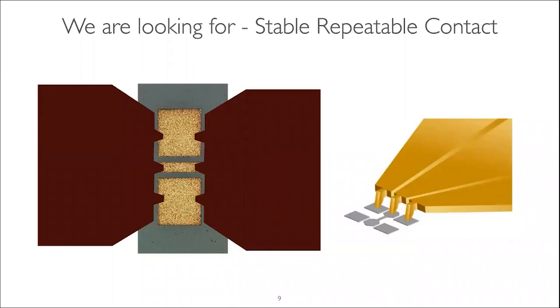You want the probe tip to land correctly on the pads on the device so that you can calibrate accurately, and so that you can measure accurately. If you have one pin that's in the air, that's not landing right, or it's moving, or there's oxidation, this is a nightmare. So this is something that takes some time, and integration on a probe station is a big thing.